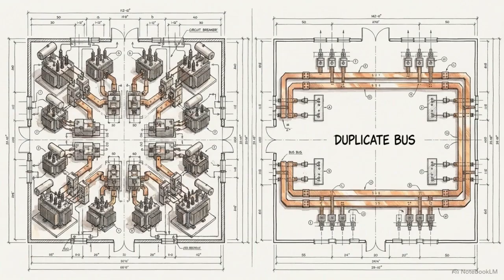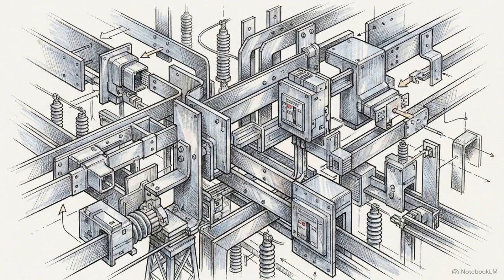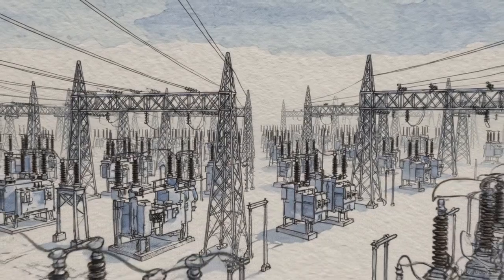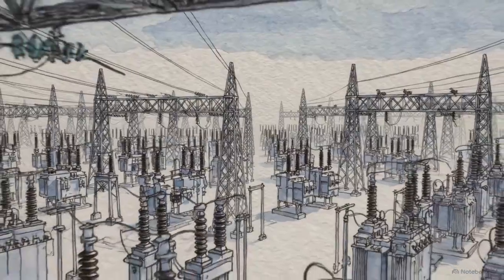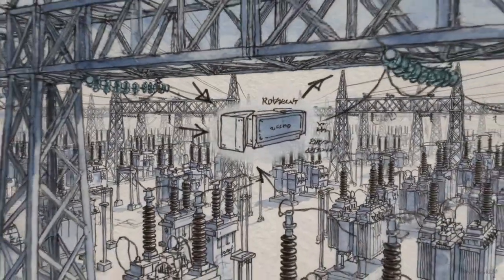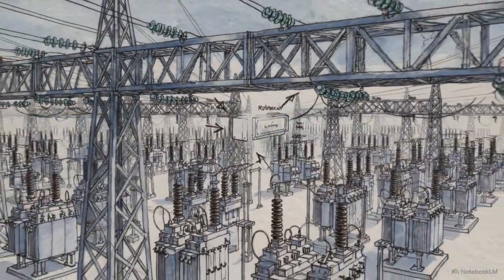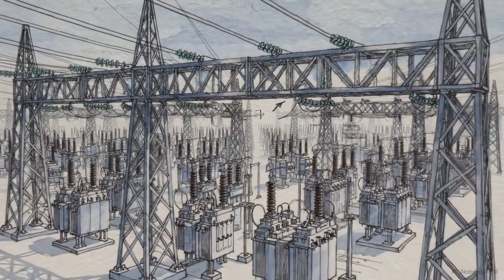However, there is a massive constraint. Achieving this level of redundancy requires doubling the physical footprint of the busbar, heavily increasing raw material costs, and demanding a complex array of interlocking switchgear. While pure duplication successfully buys reliability, it creates an unsustainable geometric scaling cost when applied to massive 400 kV interconnects.